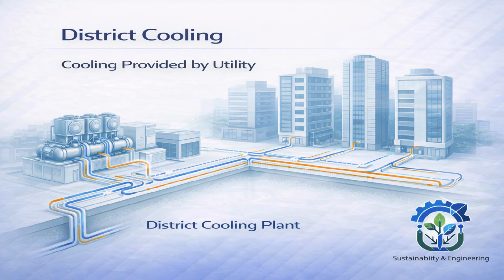Let's understand why district cooling exists. District cooling exists for one main reason, that is large scale. When developments become very large, such as high-rise towers, master planned communities, and city districts, it becomes inefficient for every building to run its own cooling plant. A centralized utility can operate large, high-efficiency chillers, optimize energy use across many buildings, and manage peak demand better than individual systems. This is why district cooling is heavily promoted in dense urban developments.